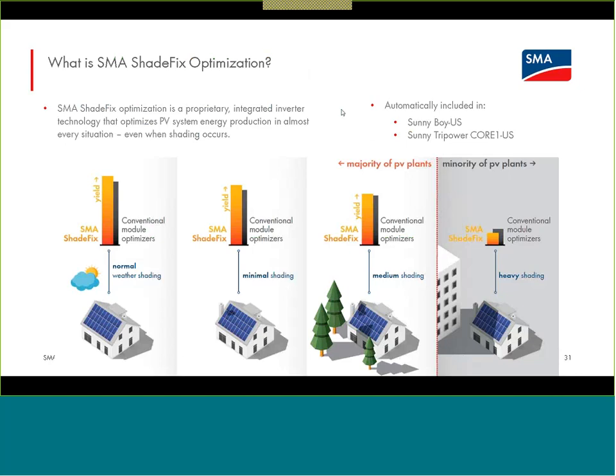or existing plants. We talk about, for the U.S., compliance with rapid shutdown. There are some very stringent requirements for rapid shutdown that, even if the CORE1 can be placed very close to the array, now we are generally required in most states to have module level separation when rapid shutdown is triggered. So we have a per module device, the TS4RF, that can work with the new CORE1s very directly to achieve that compliance.